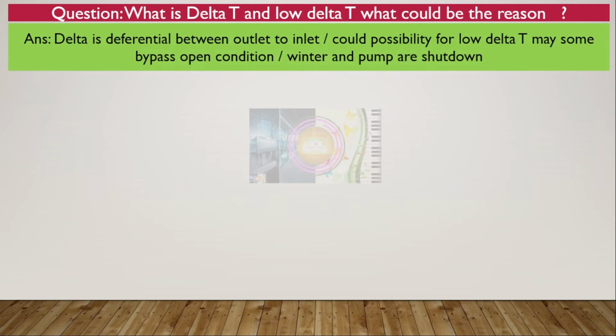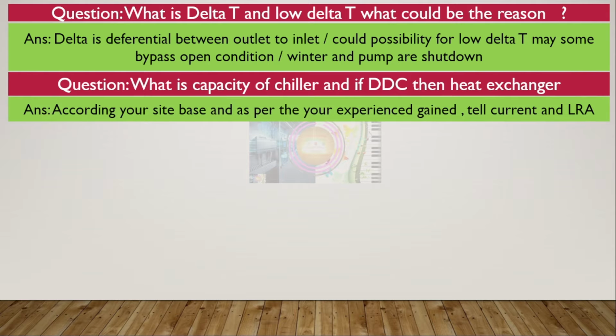What is a delta T and a low delta T? What could be the reason? Delta T is the differential between outlet and inlet. Possible reasons for low delta T may be a bypass open condition, winter, and a pump being shut down.